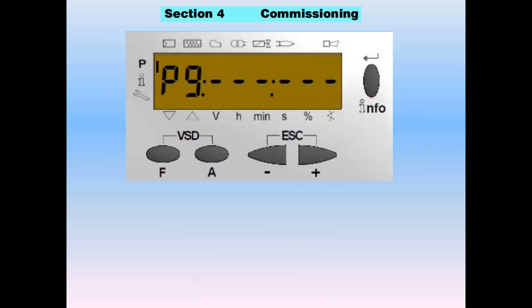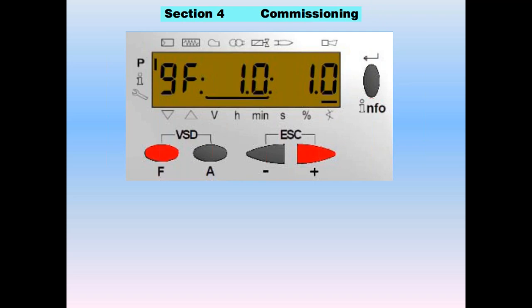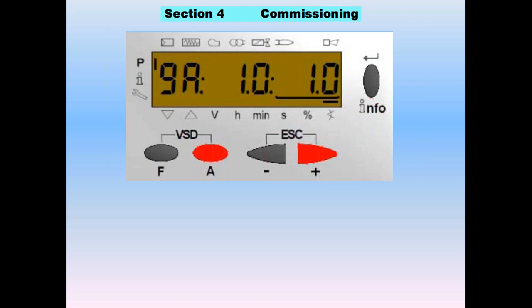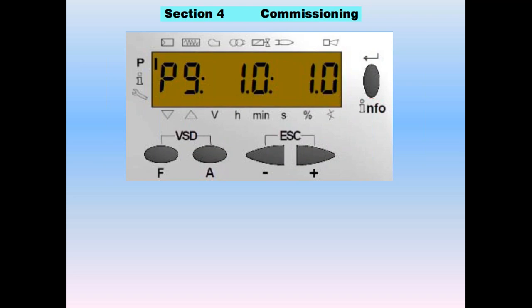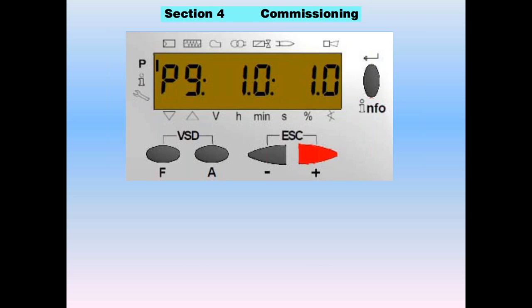Once the ignition setting is adjusted, press plus to continue. You'll be prompted for a high fire setting — we're trying to bracket in the fuel curve. My suggestion is to enter the same values as you did on the ignition setting. Once the burner is lit, go out to high fire and find the high fire part of the range, then build a curve on the way back down. There are many ways to build a curve, but this is the easiest unless you know exactly where your high fire will be. Here we have P9 set with one degree of air and one degree of gas. High fire setting is now complete.